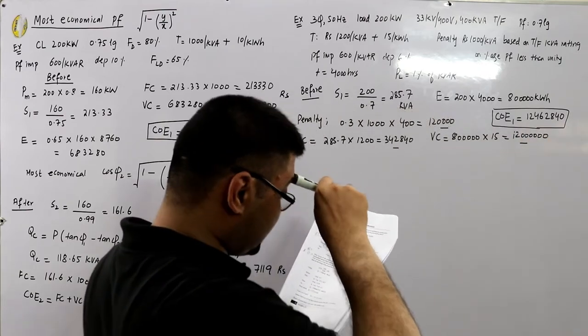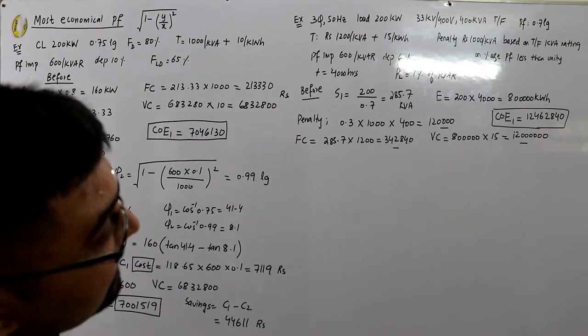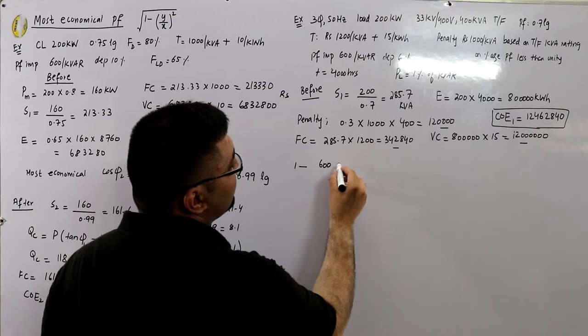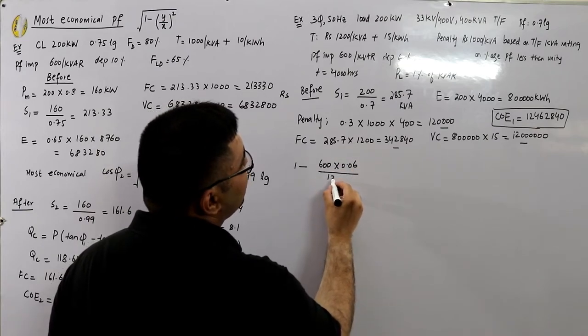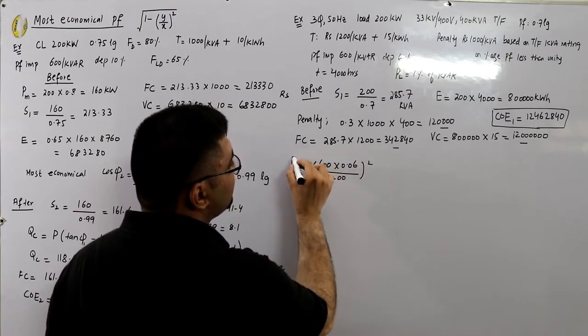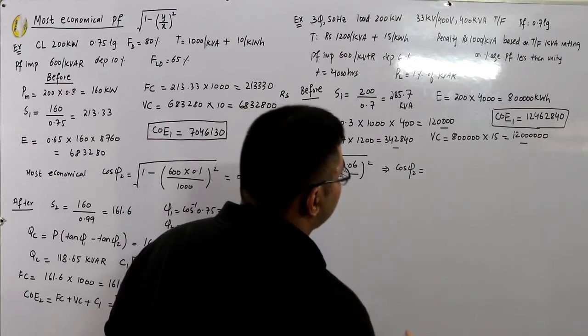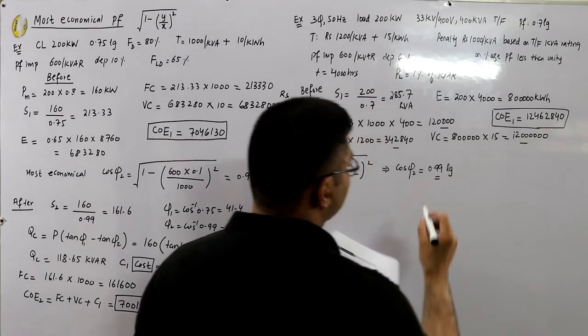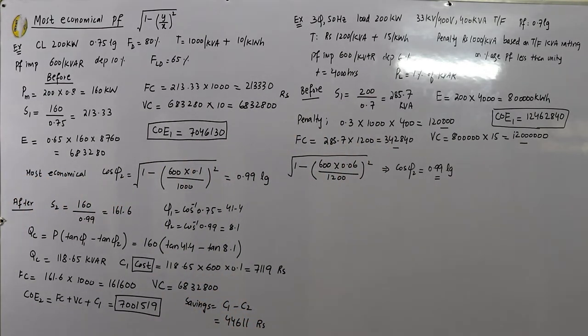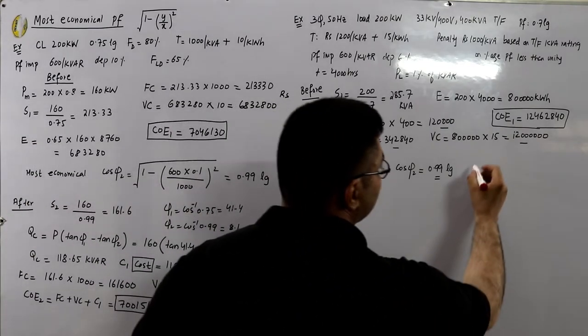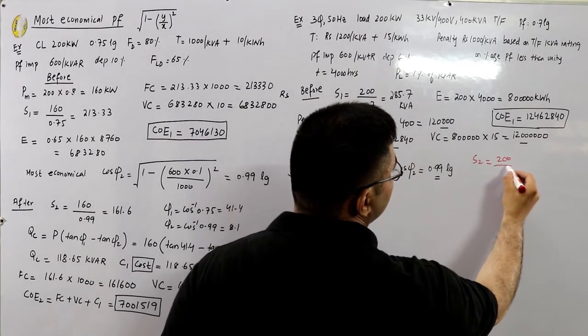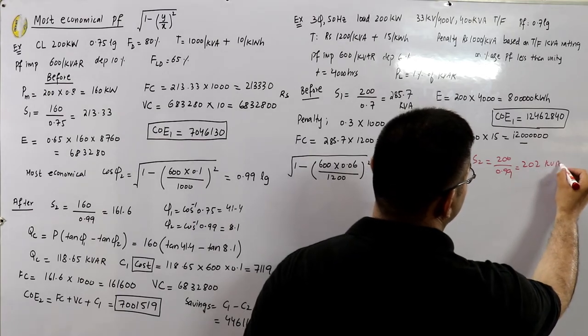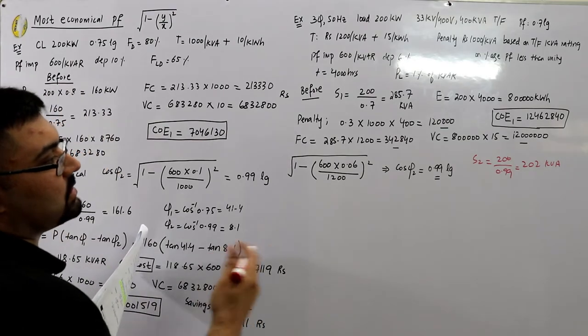Now find the most economical power factor: cos φ₂ = square root of 1 minus (600 × 0.06 / 1,200)², which gives 0.99 lagging. After correction, S₂ = 200 divided by 0.99 = 202 kVA.